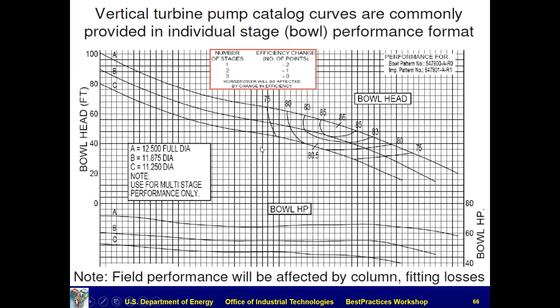And so if you were selecting, say right here on this 60 feet of head, whatever that flow rate is, you have the same flow rate through each bowl, but if you had 3 bowls, you would have 3 times 60, you would have 180 feet of head, because it goes through one and then the other and the next, and each one boosts the pressure by that amount. Okay, and so it also affects the efficiency determination.